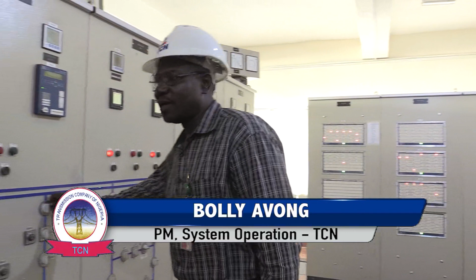There is the 75 MVAR reactor that is connected to the bus 1, and then there is also the 150 MVA transformer that is connected. So it is the 150 MVA transformer that transforms the voltage from 330 kV to 132 kV. So at the 132 kV, for now, we have one transformer that transforms the voltage from 132 to 33 kV.